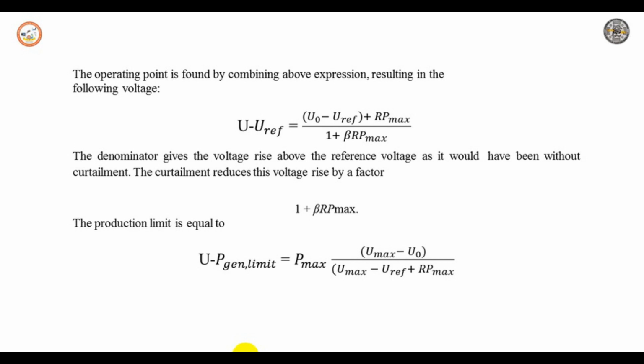Some units may not be able to curtail their production, and they will instead trip completely. The remaining units will then reduce their production by a somewhat smaller amount. When multiple units are connected at different locations, the curtailment is still shared, but no longer in proportion to the unit size. Instead, the local no-generation voltage and local source resistance impact the sharing. It is still possible to obtain closed expressions for the resulting voltages and production limit, but those are complicated expressions and do not give much additional information. So the two examples are given here.